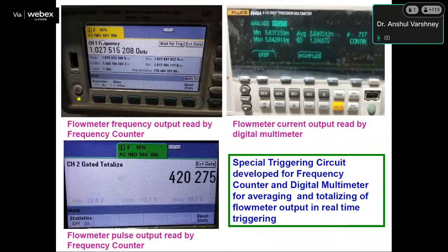This is the frequency counter. Every flow meter has two types of output, either frequency output or current output. For current output we are using this digital multimeter, and for frequency output we are using the frequency counter. The special triggering circuit has been developed for the frequency counter and digital multimeter for averaging and totalizing of flow meter output in real time triggering.